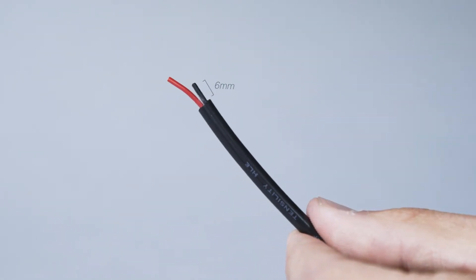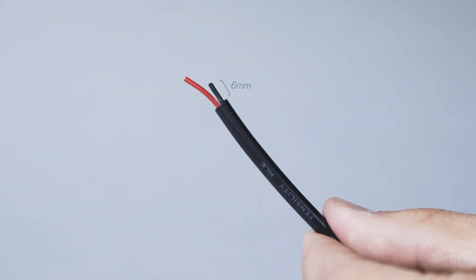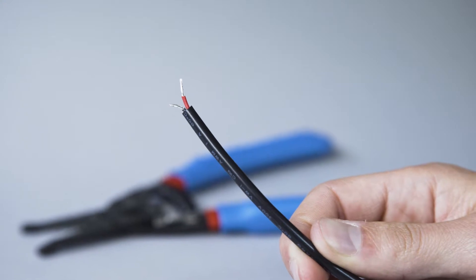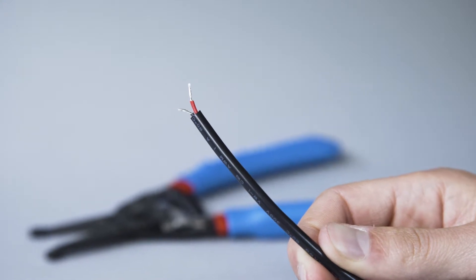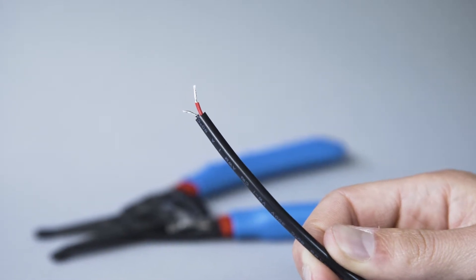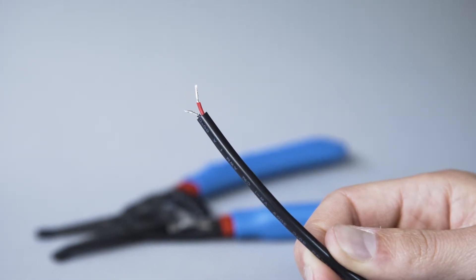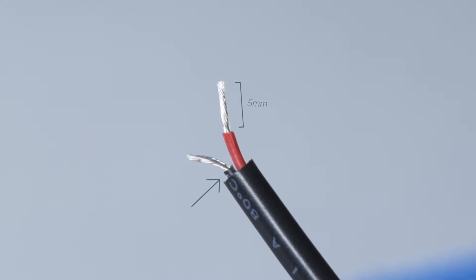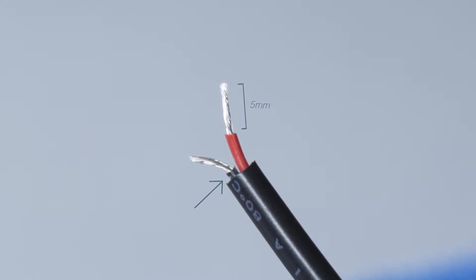If you are using a one conductor shielded wire, process it to the same length. Strip 5 millimeters off the positive insulated wire and strip the negative insulated wire as close to the base of the outer jacket as possible. Make sure the strands are twisted together.